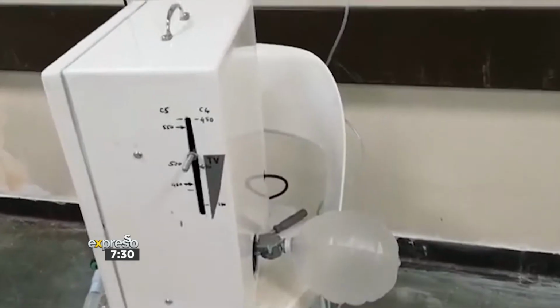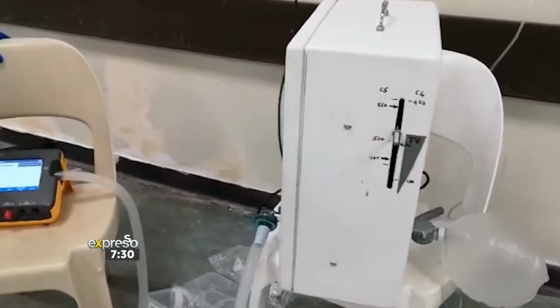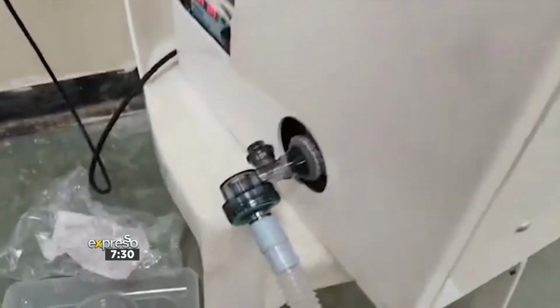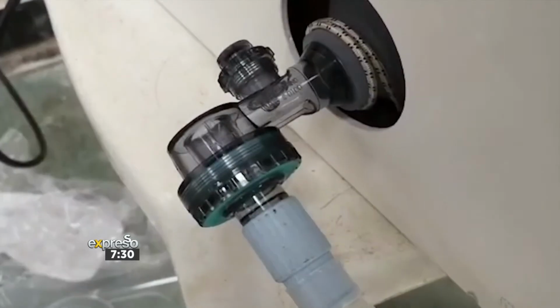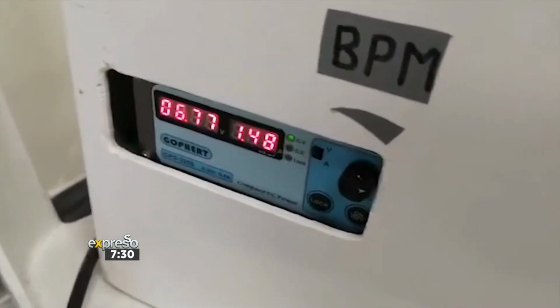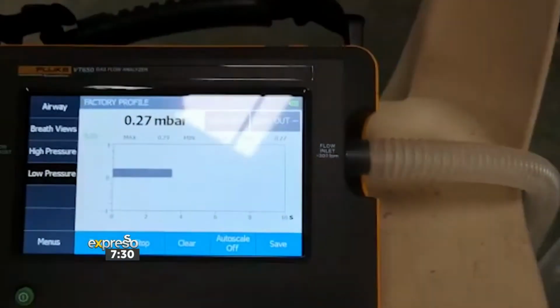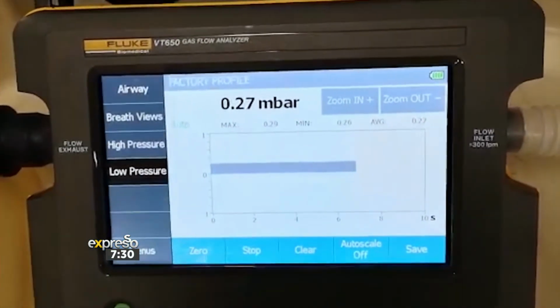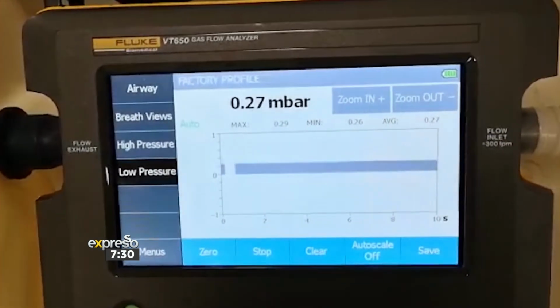And you've come out with an incredible innovation, an incredible invention as well. This machine that is named the SaveVent. It's a mandatory mechanical ventilator, I understand. Now, can you further explain to us what exactly that means and what makes this ventilator so unique to what is currently being used in our hospitals? Yes, so this ventilator is what they call a volume-controlled mandatory ventilator. So it provides the breathing automatically at a set volume. And the volume is controlled between, say, 400 and 500 milliliters per breath. The machine automatically provides that breath at a certain breathing rate, which they call the breath per minute. And that is adjustable as well as the volume on our device.